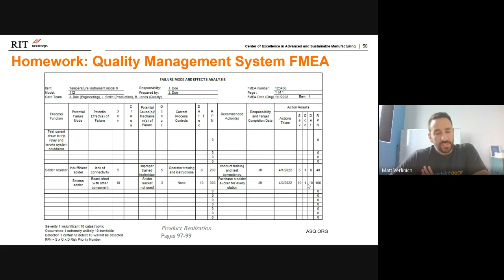Detection means how often do you expect to be able to catch it if it does happen, based on your testing protocols and the equipment that you have available to you. 1 is certain to detect, and 10 is there's absolutely no way that you'll detect it. When you multiply all those things together, you get your risk priority number, which means the higher that number, the more you should make sure that you have a plan in place to identify, catch, and mitigate those types of failure modes. This is a document you'd want to put in place once your design is fairly finalized, and it's going to be heavily based on your requirements and your operating environment, as to what type of harm you might potentially do and what you're trying to mitigate.